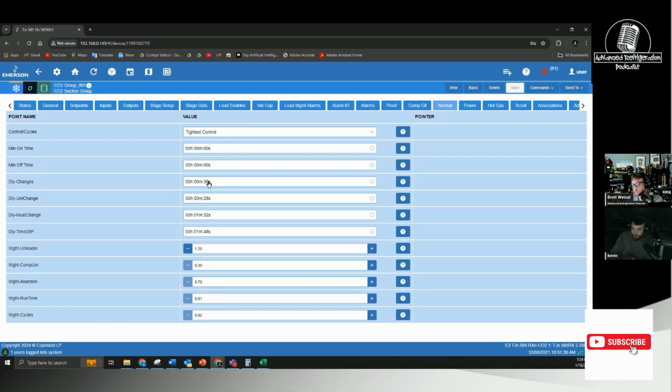Those can be directly related to the suction group. If the compressors are cycling, the BGV is going to be cycling, and the HPV is going to be cycling. It's the chicken or the egg with this. Sometimes I will start with the suction group in defrost before I even try to rein in the BGV or HPV, because you're wasting your time trying to do it the other way. Because one's chasing the other.